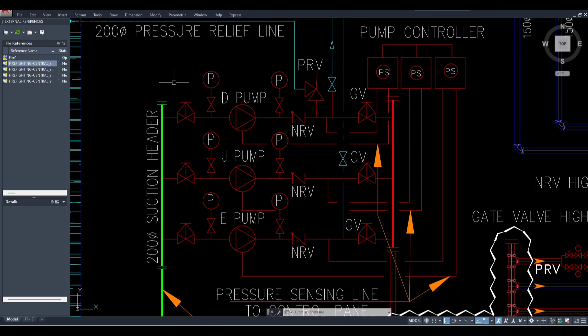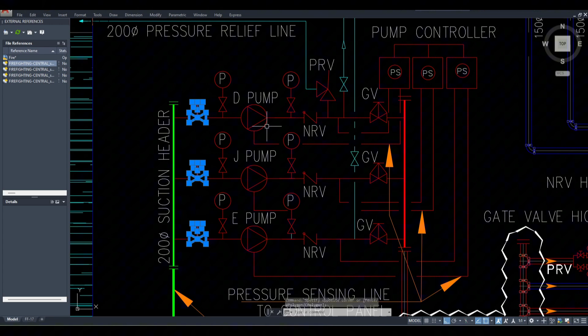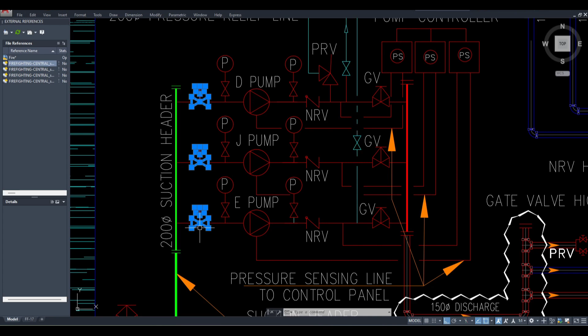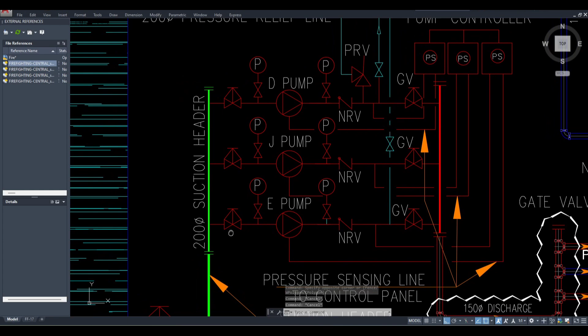This is the first thing you have to check: are the pumps connected in parallel sequence? Parallel means all are connected from the same header, and each connection has to be given one isolation valve. This is the simple rule. If any connection is not given in that way, it means something is wrong.